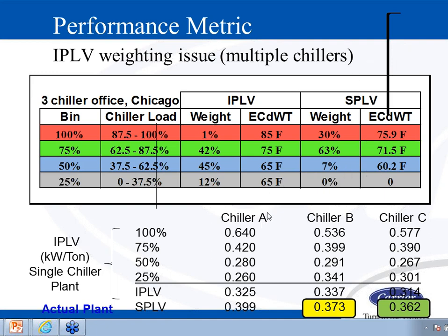When we look at the system part load value, we basically have 0.399 for Chiller A, 0.373 for Chiller B, and 0.362 kW per ton on Chiller C. So you have to analyze the chiller plant as a whole. The 25% load point almost never happens. The 50% load point has very few hours, and the overall life cycle cost winner will be the 75% load point in most multiple chiller plants.